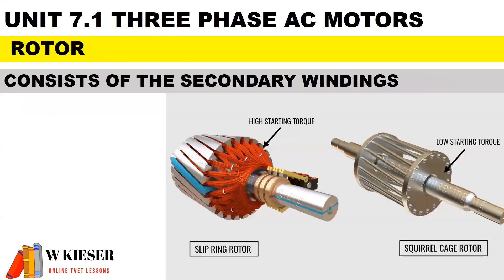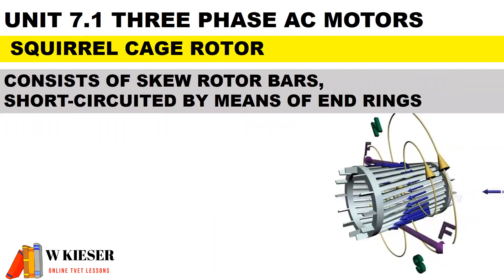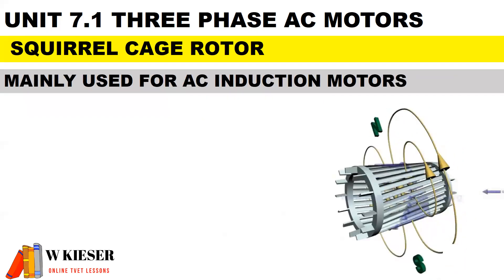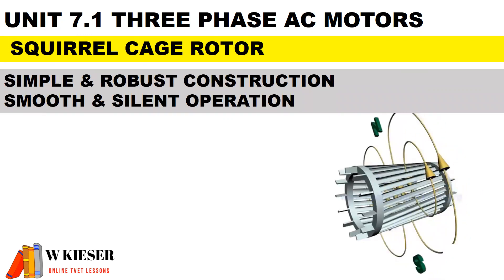In terms of the rotor, it's the rotating part and consists of the secondary windings. We get two main types of rotors: a squirrel cage rotor and a wound type rotor. For the squirrel cage rotor, it consists of skew rotor bars, usually made of aluminum, short-circuited by means of end rings. They are mainly used for AC induction motors. They have very simple, robust construction with smooth and silent operation, and also require very little maintenance.